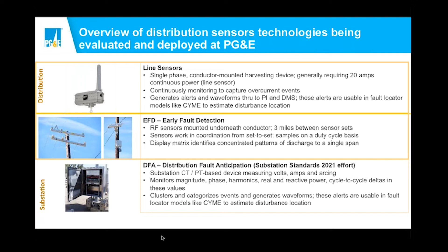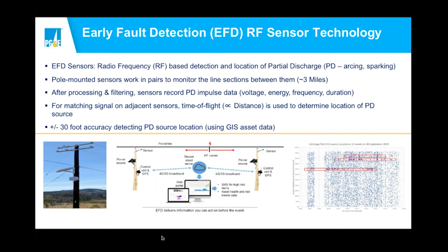In the next couple of slides, I'll give more details on the EFD and DFA technologies. This slide does a double click on EFD. If you look at the picture on the left, the sensors are mounted right below each phase of the conductor, powered by solar panels, with the control unit right below it. In the middle image, the red fault indicators on the line are arcing, sparking faults that travel through the conductor and get picked up by the sensors. These sensors can then coordinate with each other and leverage locational information, because they have GPS, to triangulate exact locations. What we're seeing is about plus or minus 30-foot accuracy with these sensors.